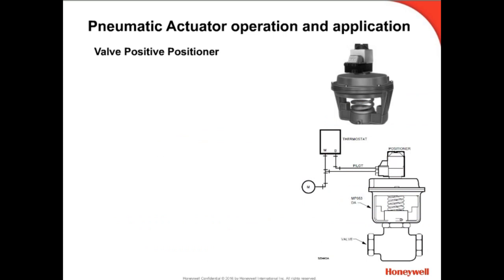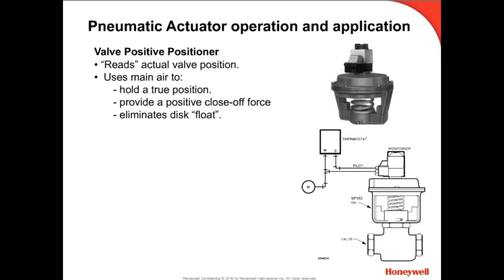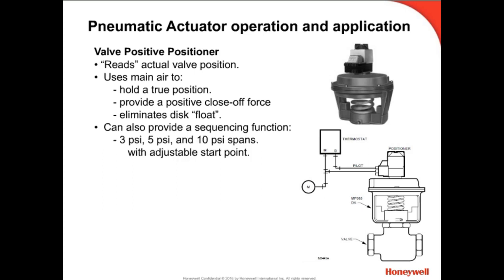When additional control power is required, valves with a positive positioner can be applied. This valve actuator positioner is connected to the actual valve stem and will provide additional control power to the actuator diaphragm. A controller branch-line signal pilots the positive positioner relay. The relay compares this signal to the actual physical valve position, then adjusts main air directly to the actuator diaphragm to hold the valve true to the control signal. It also has a built-in sequencing function for sequential valve operation to meet system control logic strategies.